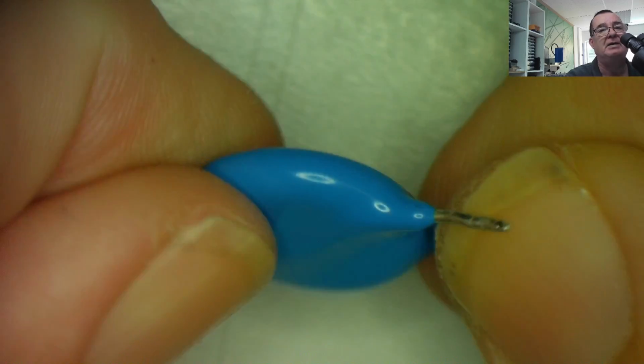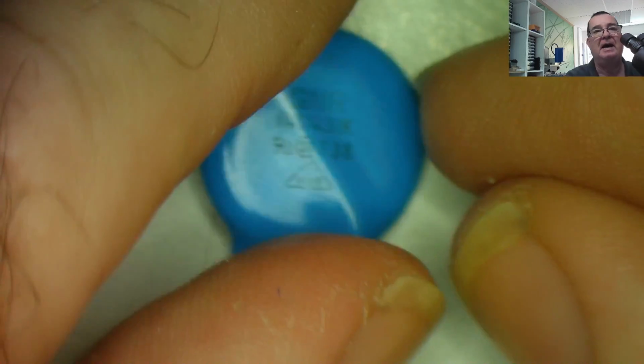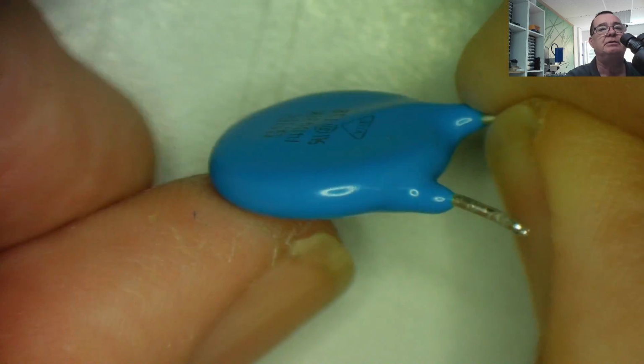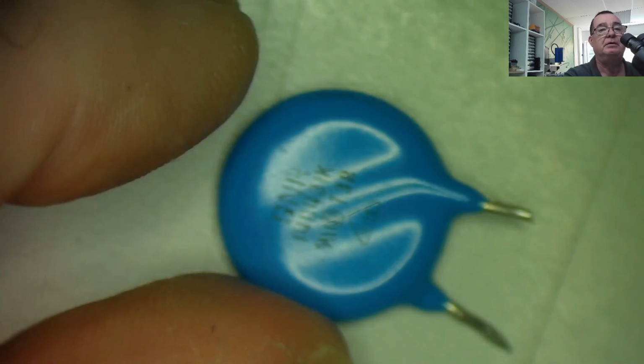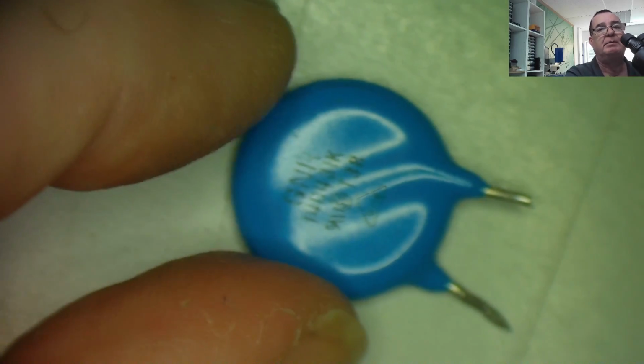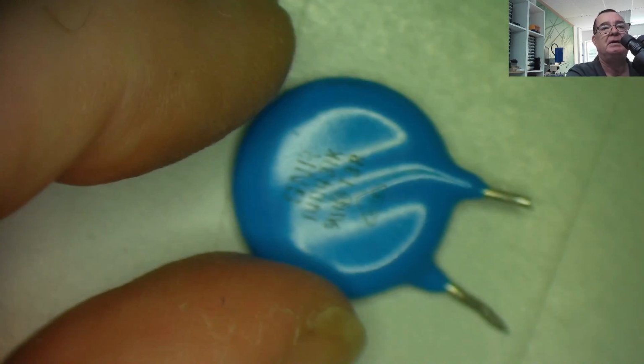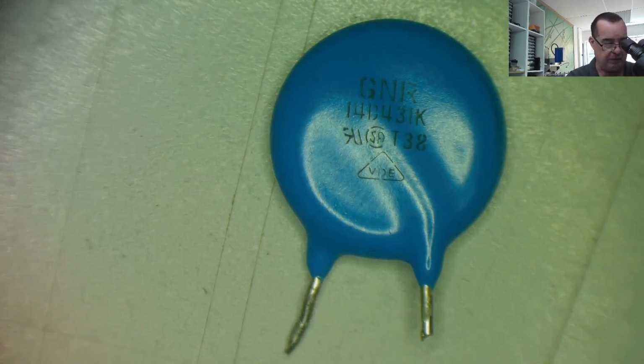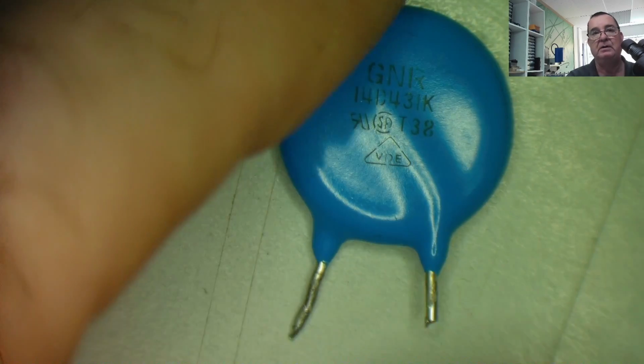Because this is a protection device, we can actually connect our device with this missing. We can take this out of the circuit and power it up. So we no longer have the protection, but we can at least test to make sure that nothing else has gone faulty in our circuit. And then obviously I need to replace this before it goes back to the owner if it's still working. So to do that, I'll just do two things.